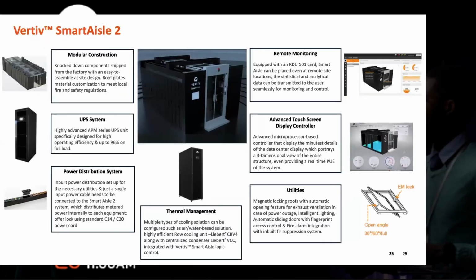The systems in this SmartAisle include all your different components, the UPS, the monitoring solution, and one good feature is the roof lock. Whenever there's a power outage, the heat inside the data center will start going high, so the roof will drop automatically to allow fresh air to reach the equipment before power is restored. Also, if there's a fire incident, this roof will drop down to allow the FM200 fire suppression system outside to sprinkle into the data center.